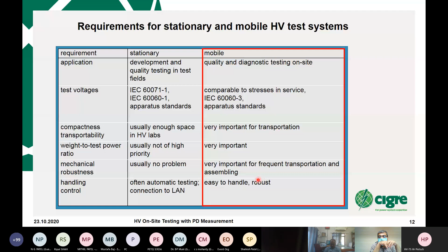Stationary is normally known to all who have experience with high voltage testing, commissioning, factory tests, and so on. And for mobile, there's another standard which defines the wave shapes and the tolerances which are allowed, and normally they're a little bit higher than if you are inside the factory. And of course, the equipment has to be suitable for transportation. Suitable means from the size point of view, weight point of view, accessibility of the roads to the site, and so on. And it must be very robust, because there's not a smooth highway to every place.